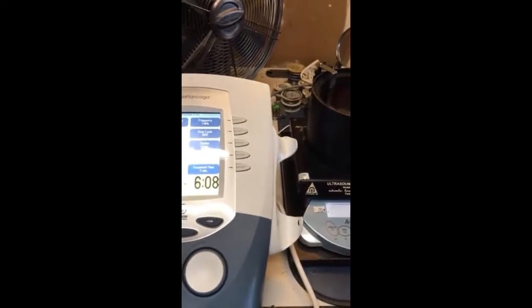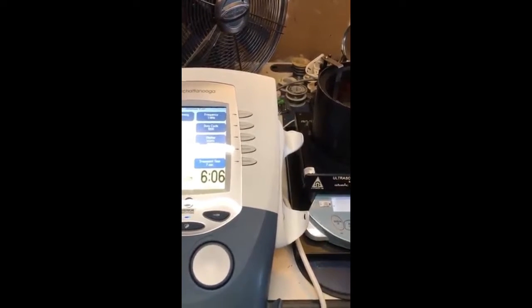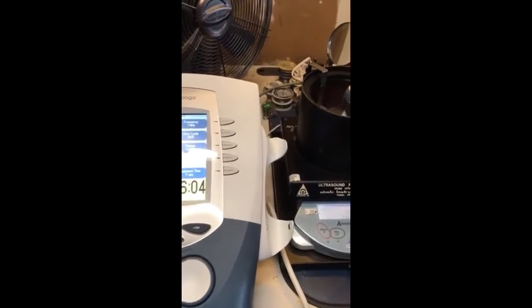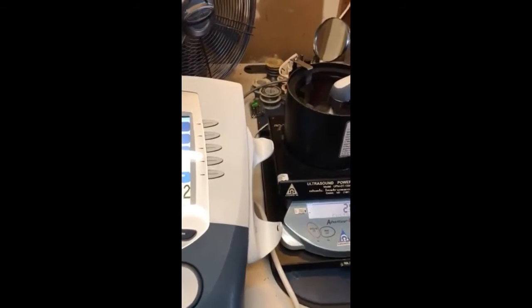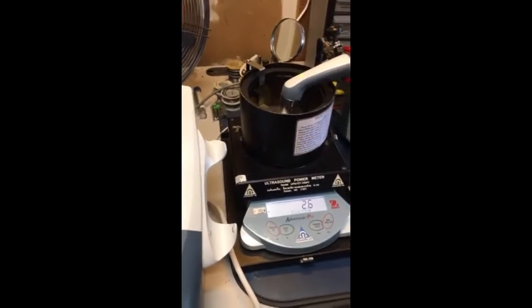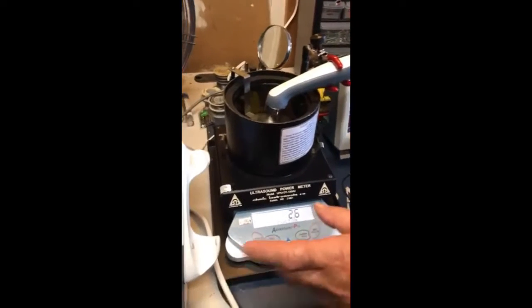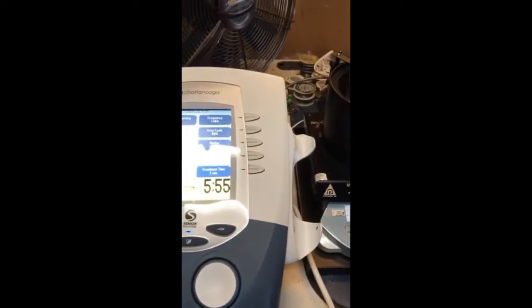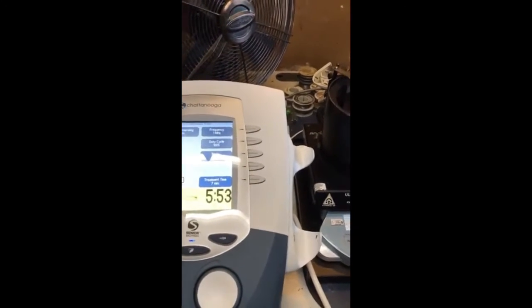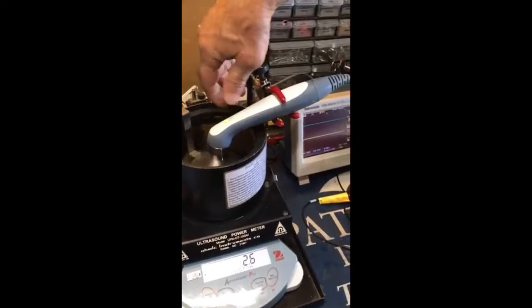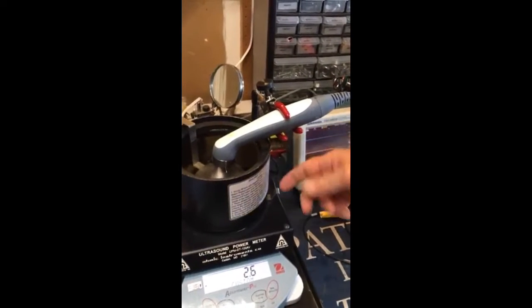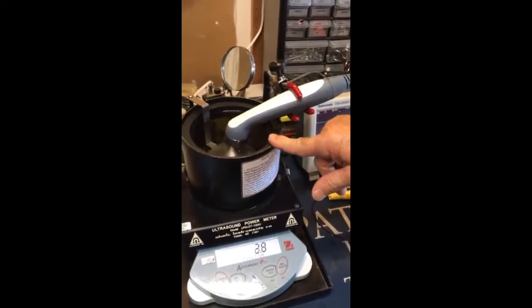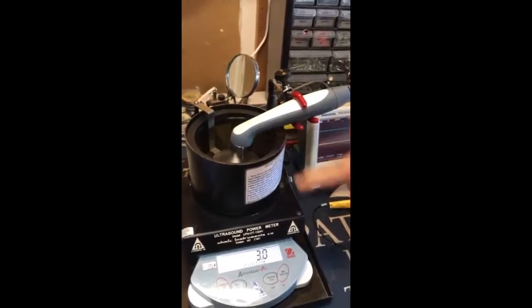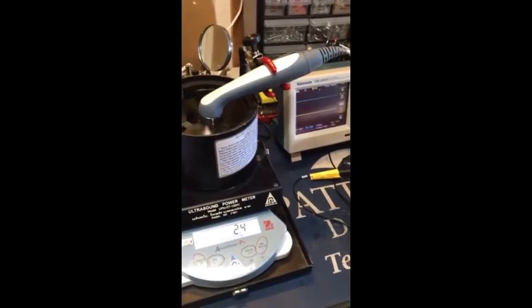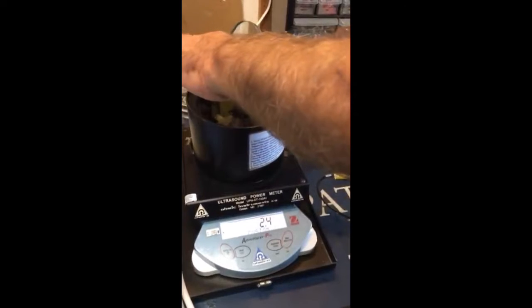It's not the cord giving you an issue, which sometimes it is. Just by wiggling the cord, you'll see it didn't change. You know, that's not what's going on. The other thing is that a lot of times the sound head or the holder is pressing down on this. You'll see if you press down on it, it's going to change. And sometimes that happens.